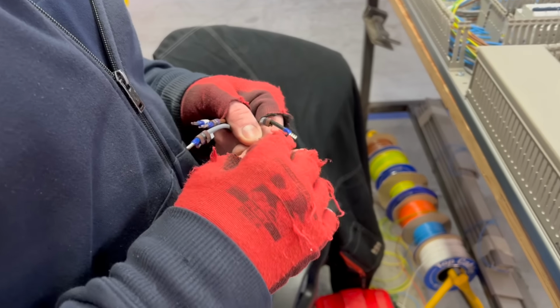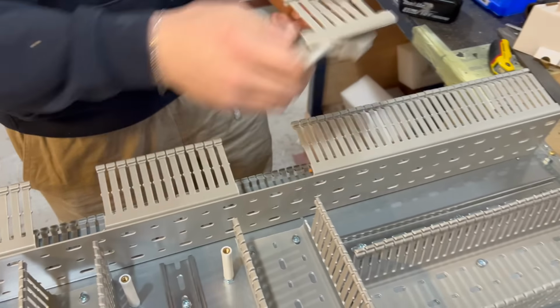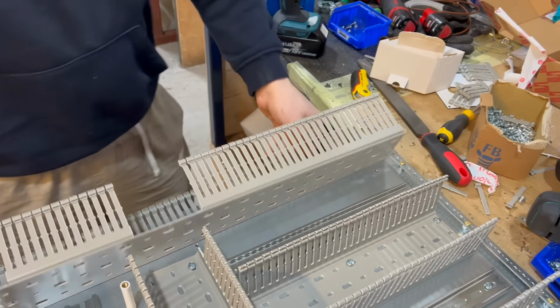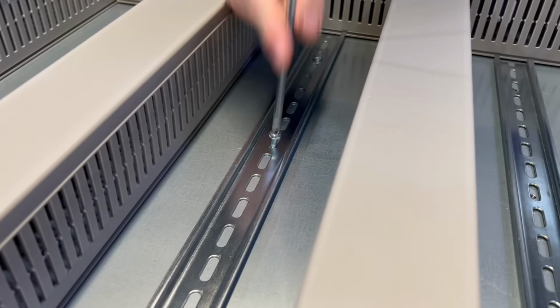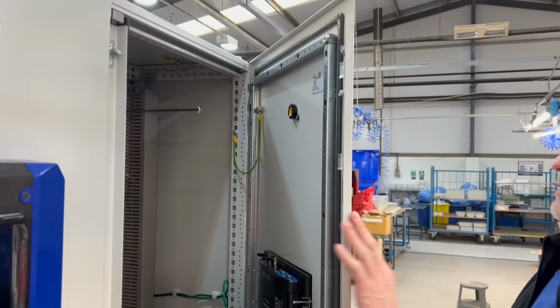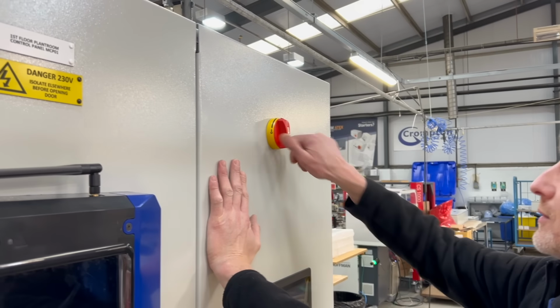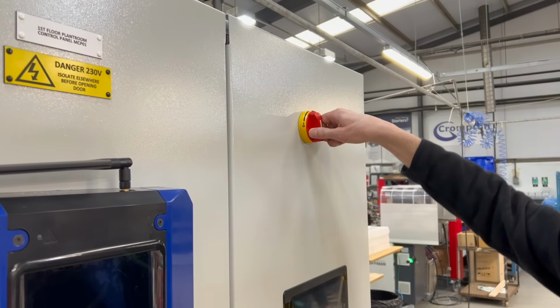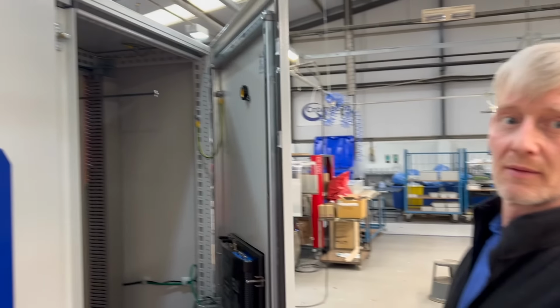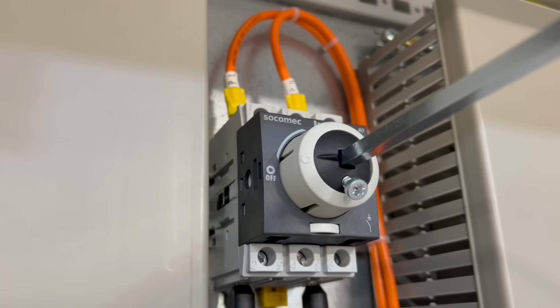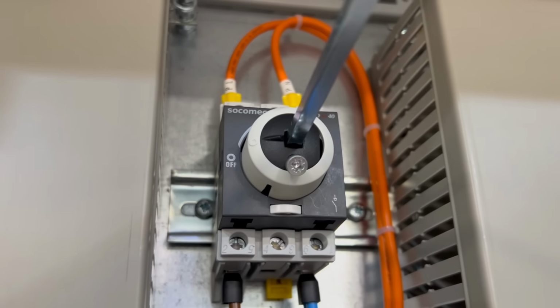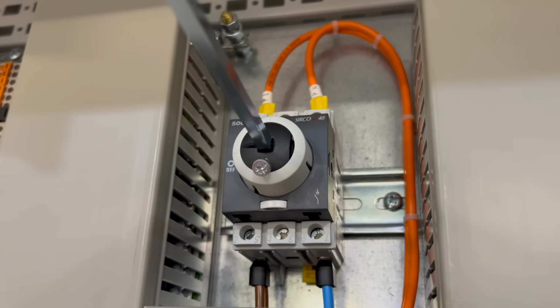Now, because no two BMS control panels are the same, we're going to look at various different components that you might find inside one, even if they're not all present on this one. Depending on the type of panel, it may or may not have one of these, the isolator. This is the device that will prevent anyone getting inside a panel while it's live and accessing any live parts. It will usually sit on the back plate of the panel, where the isolating of the conductors actually takes place.